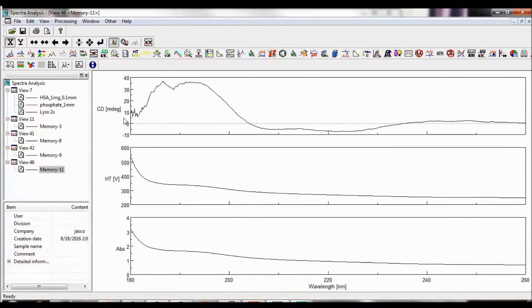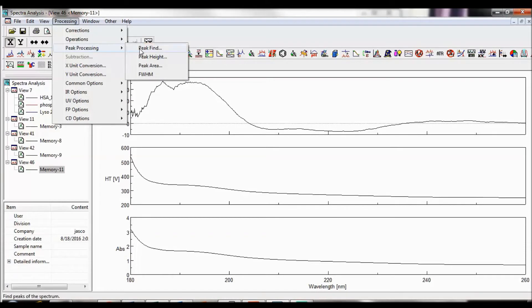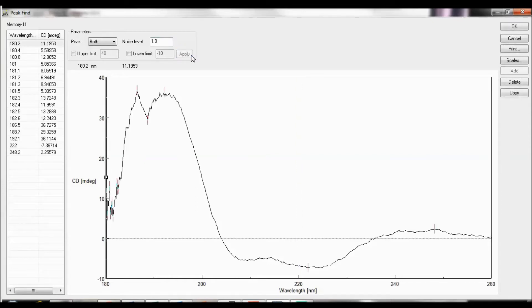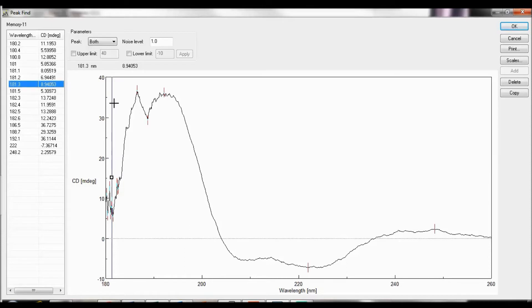To locate a peak in a spectrum, select Processing, Peak Processing, Peak Find. The Peak drop-down list specifies whether you would like to locate peaks or valleys in the spectrum. For CD data, select both. Specify a value in the Noise Level box to determine a threshold used to recognize the top and bottom of a peak. If the difference between the top and bottom of a peak does not meet or exceed this value, the peak will not be recognized. The upper and lower limits when searching for peaks can be specified in the upper and lower limit boxes. Clicking Apply executes the peak find using the specified parameters, and a red bar will appear at the located peak positions. The peak find results are then displayed on the left in the peak table. Clicking on a particular peak value will cause a vertical cursor to appear at the selected peak in the spectrum display area.